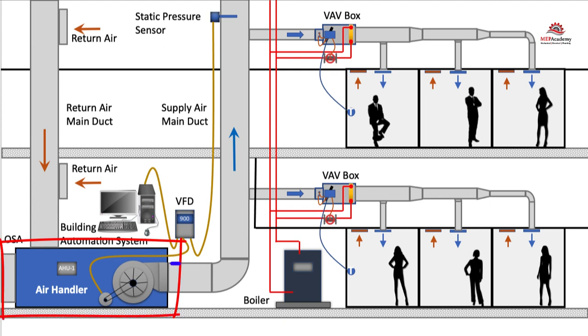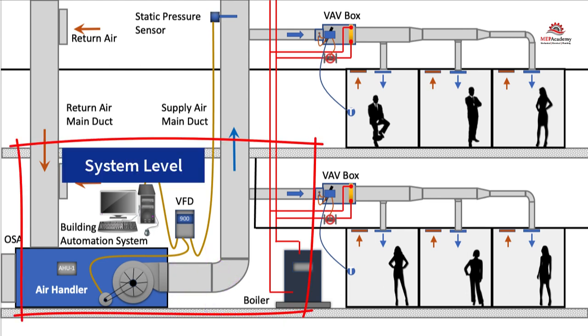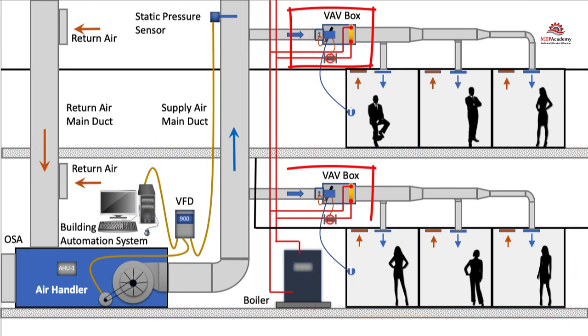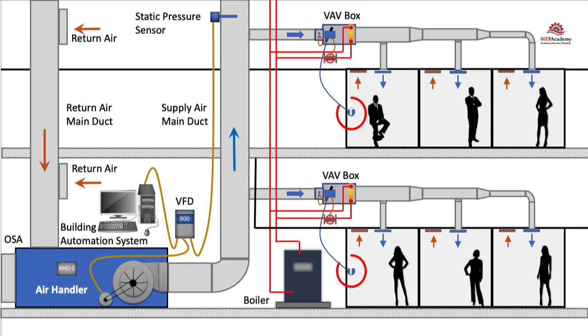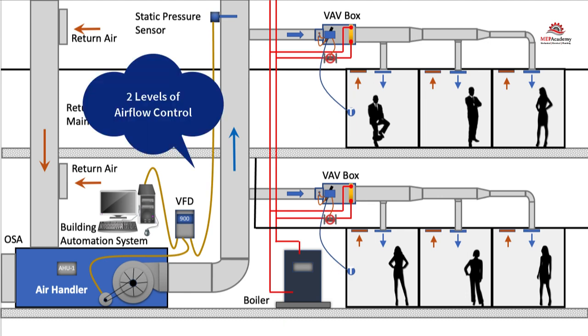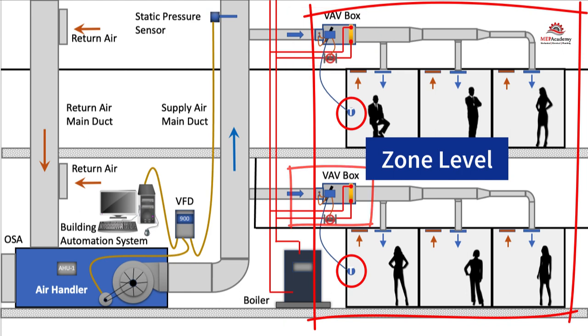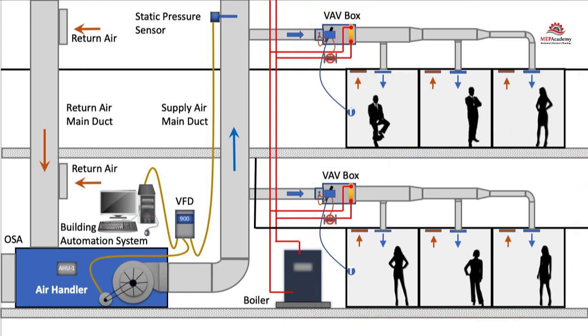The air handler varies the amount of air flow, CFM, at the overall system level based on demand required by the zone level VAV boxes. The VAV boxes regulate the flow, CFM, to a zone in relation to the demand of the temperature sensor in the space. So you have basically two levels of air flow control. It starts with the VAV box at the zone level where the room temperature sensor determines one of three modes of operation. The next level of air flow control happens at the air handler, which responds to what is happening to all of the VAV boxes attached to the system.